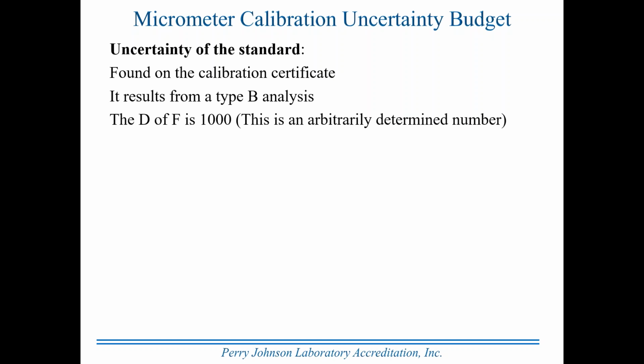Some people would argue that it has limited importance in certain calibrations, highly significant in other calibrations. I tend to agree with that. I also would say, though, that if you're doing your budgets in an Excel spreadsheet, the time it takes to perform the calculation is not significant. It doesn't slow you down any. Once you build a budget and include this calculation in it, it's there every time, and it's done literally at the speed of light, so it has no performance impact on you.